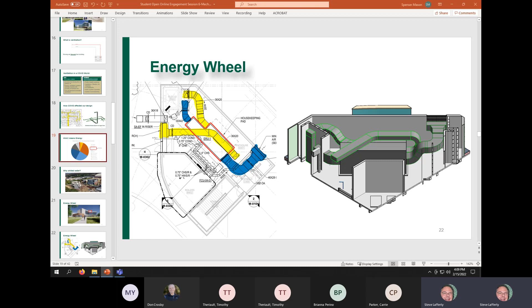This is really where the magic happens, in this wheel right here. This is a cross section, so you're seeing the wheel edge on, but there is a wheel that rotates in and out of the page between the exhaust and outside air streams. The wheel is made of a papery, almost tissue-papery media that's able to absorb heat and, significantly, absorb moisture.